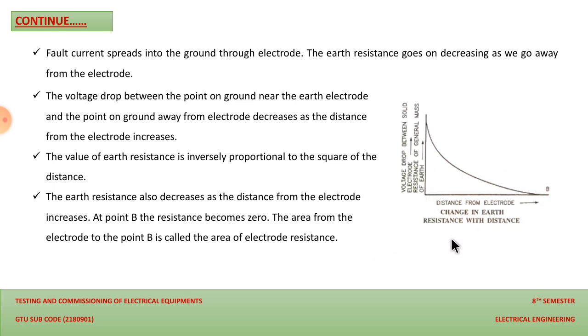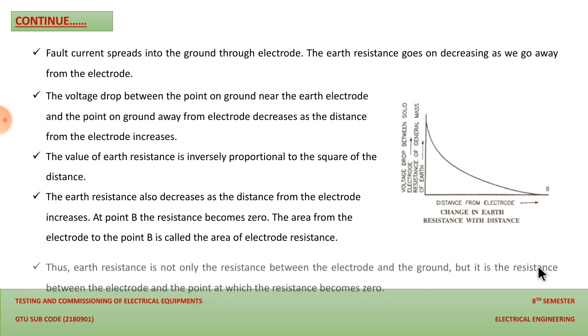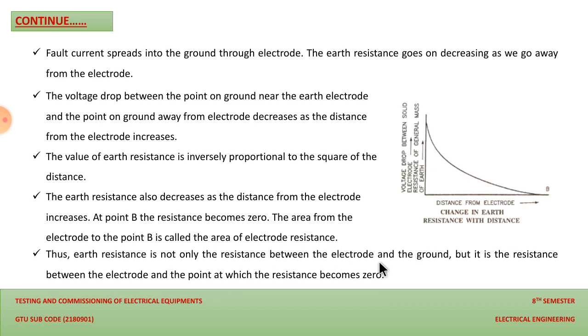We should keep the minimum resistance of this portion, so that we can discharge that heavy current, or we can say potential, whenever the earth fault occurs. And thus the earth resistance is not only a resistance between the electrode and ground, but the resistance between the electrode and the point at which the resistance becomes 0. So the point where the resistance becomes 0 and the point where the electrode is placed is the most important place, where we should keep the earth resistance as low as possible to fulfill the work of the earthing rod.